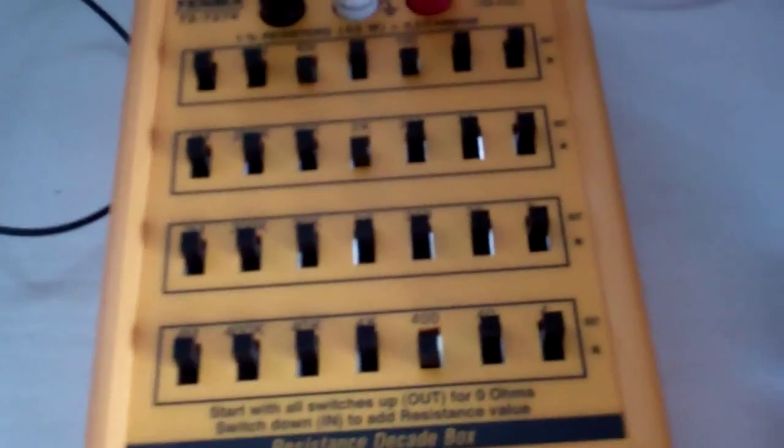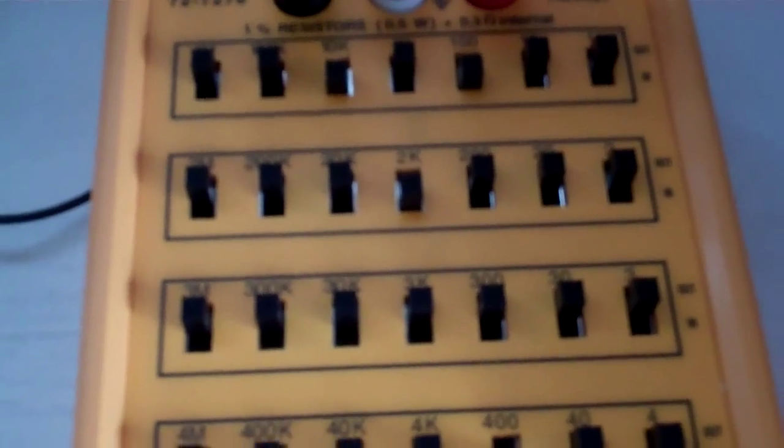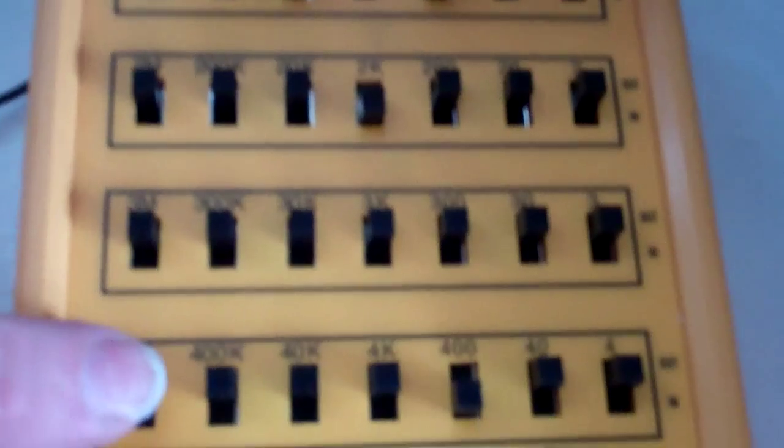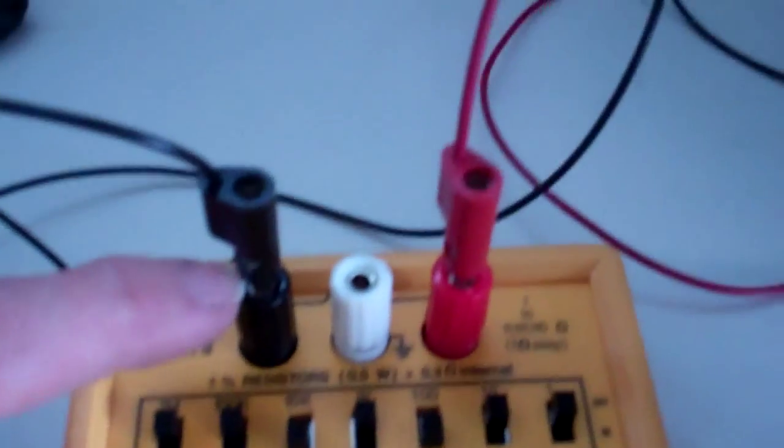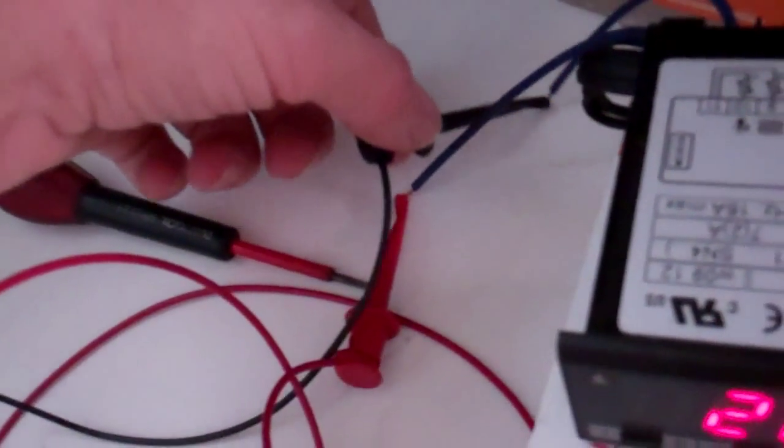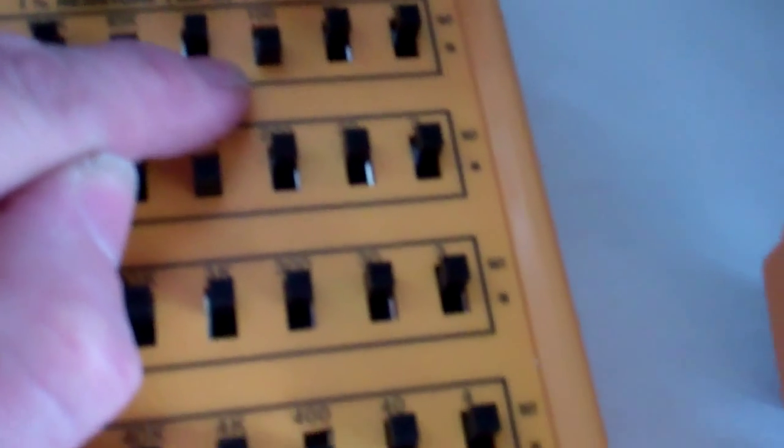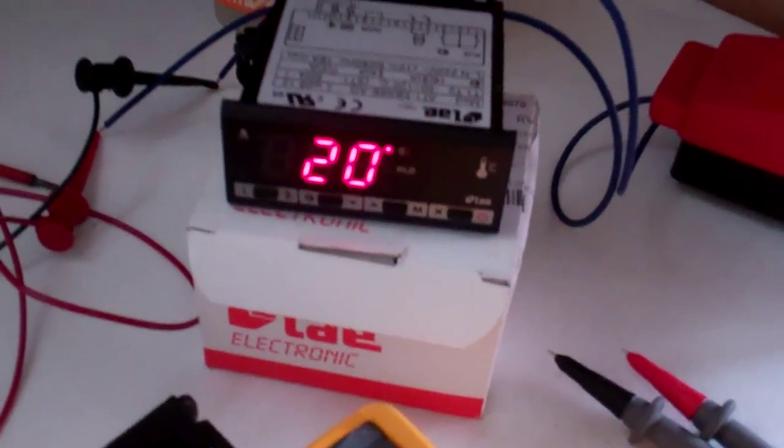But on the air temp probe I've got this decade box which is just basically four banks of resistors with switches to switch them in and out of circuit. And a couple of outputs and I've got them clipped under the probe connections and it's set at 10K, 12K, 400 and that says 12.5K and that is now reading 20 degrees.